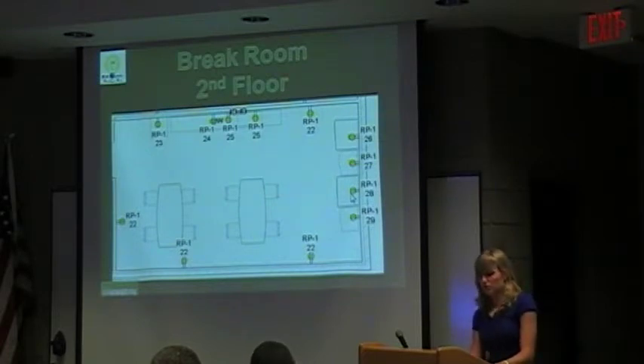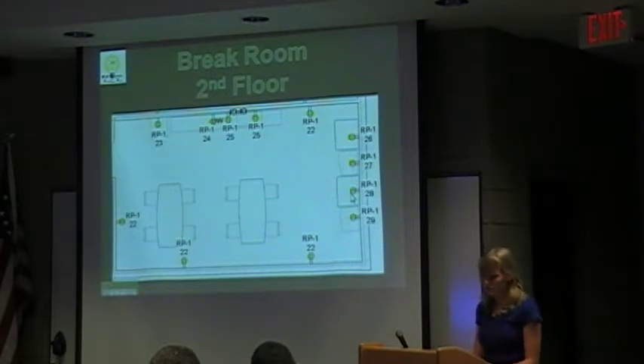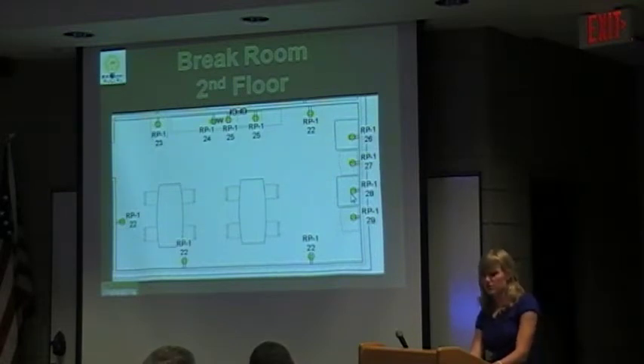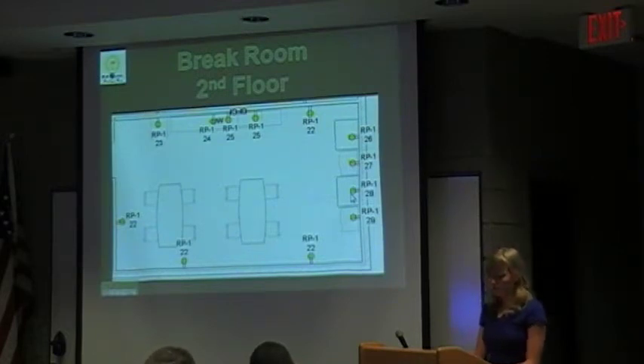In the break room, there are quite a few dedicated circuits. It's basically treated like a kitchen. So circuit 23 feeds just the refrigerator, circuit 24 feeds just the dishwasher, and then circuit 25 feeds the GFCI protected countertop receptacles. And then each vending machine also has its own dedicated circuit. And then circuit 22 is just basically your convenience receptacles.